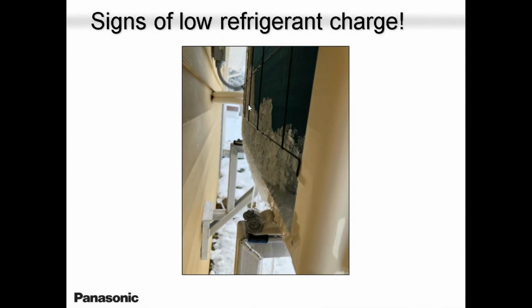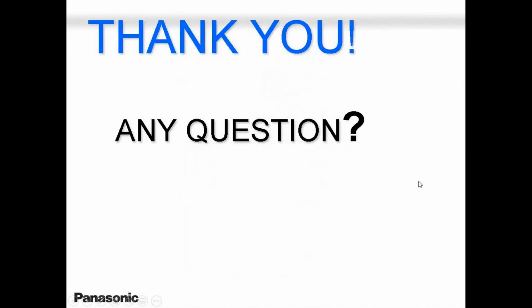You see this picture I took out? I got a picture from a contractor last week. This system was low on refrigerant. So what was happening? When the defrost cycle was performing, at the very bottom, it would not defrost because there was not enough heat coming out of that refrigerant during defrost. So I asked him to recover, do a deep vacuum, recharge, and no problem.